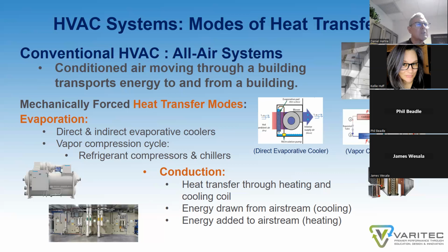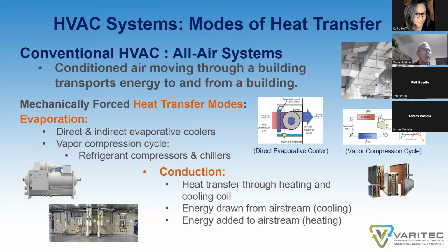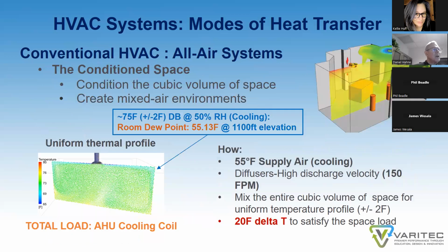The other mode of heat transfer is conduction. This is heat transfer that occurs through heating and cooling coils, where air comes into direct contact with a chilled or warm surface, allowing energy to either be removed from an airstream in cooling or added to an airstream in heating. From a room-side standpoint, a conditioned space, we actually condition the space by creating a mixed air environment. We condition the cubic volume of space. It's recommended by ASHRAE you maintain plus or minus 2 degrees of temperature set point throughout the cubic volume of space.